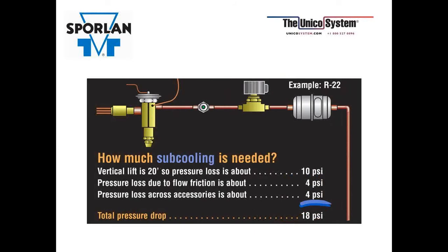to prevent the flash gas formation in the liquid line, you have to subcool the refrigerant below the condensing temperature, but how much subcooling do you need? This can easily be determined by a reasonably accurate estimate of liquid line pressure drops. The example on your screen is R22. The total pressure drop is 18 psi. You have 10 through your vertical lift, 4 through the flow friction of your line set, and then another 4 through your accessories, 2 for the catch-all and 2 for the solenoid. So your total pressure drop is 18 psi.